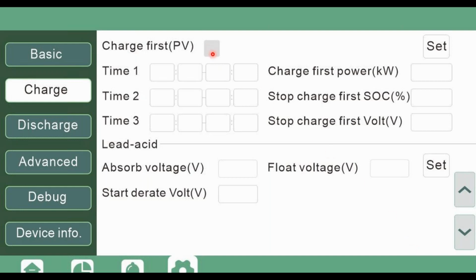But if you enable the charge first PV option, then your inverter is going to prioritize your battery first and then your loads. And if you can export, then you will export as well, unless you disable it on the basic screen, right? And you will also enable that by your time of use settings. Okay, you stipulate the charge first power, and then stipulate when you want to stop based on SOC settings.